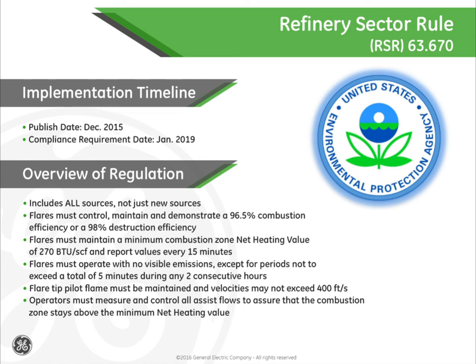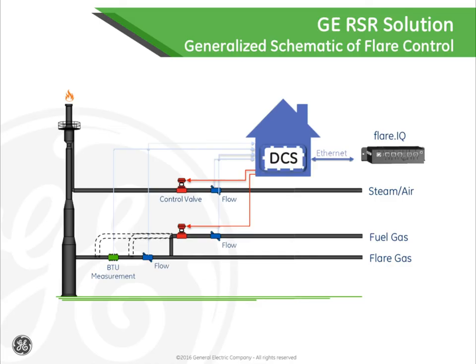Another methodology for combating this controls nightmare is utilizing software that has been developed by GE. The software, called FlareIQ, utilizes patented algorithms with access to data from ultrasonic flow meters to address BTU measurement latency resulting from the gas chromatograph. This unique approach addresses the BTU measurement latency to ensure the flare operates at the efficiency expected by the EPA, and it eliminates the need for additional equipment. Through this software package, the operator will receive nearly real-time updates of BTU content, will receive the molecular weight of the hydrocarbon mixture, and the required set points for all assist flows.